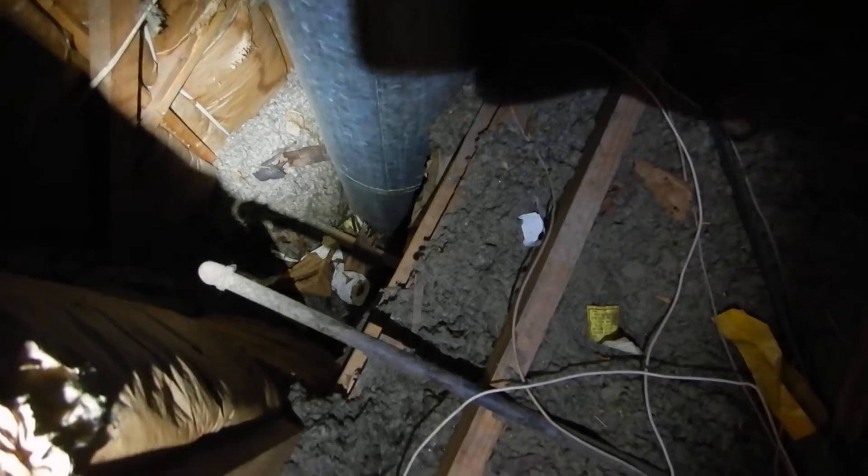Let's take a peek over here — I can't spend too much time up here. Look at all that debris. I can't see a fire blocking plate; there might not even be a fire blocking plate. There are all kinds of combustible debris inside the chimney chase, we're missing some attic insulation, and we've got short-cycling ventilation — see the discoloration up there, it's doing the same thing.